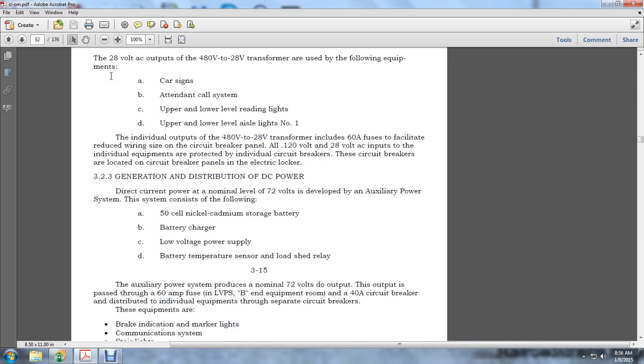The 28 volt outputs of the 480 to 28 volt transformer feed the following equipment: the car signs, attendant call system, upper level reading lights, upper level and lower level aisle lights. Number one, individual outputs of 480 volts to 28 volts. The transformer includes 60A fuses to facilitate reducing the wire size of the circuit breaker panel. All 120 volt and 28 volt AC inputs of the individual equipment are protected by individual circuit breakers. The circuit breakers are located in the circuit breaker panel of the electrical locker.